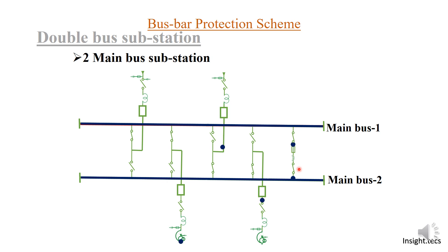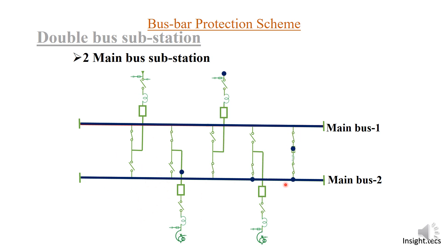Now let us consider another scenario — bus maintenance. If you want to perform maintenance of one bus, it is very easy to free that bus because all elements will be connected to bus number two. If the bus coupler is off and the isolator is open, main bus one will be completely isolated.